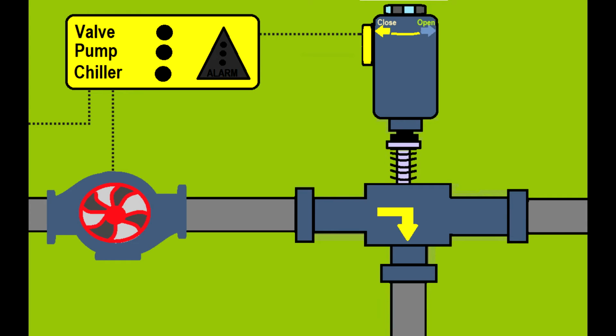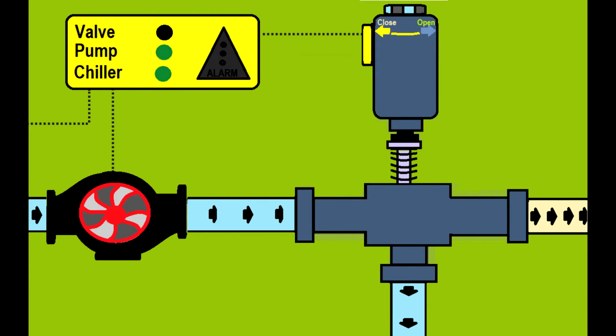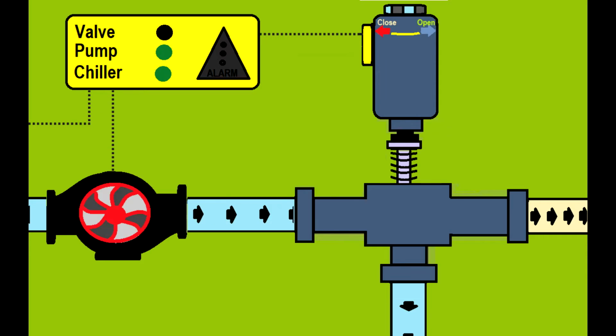And if you have a very large system, you might not even hear if the glycol runs through the system. You will laugh and say, that's simple, but I found technicians who didn't look and struggled with the valve, and not checking the pumps, or maybe the valve before the actuators, the valve which allows you to isolate the system if you want to remove some parts.